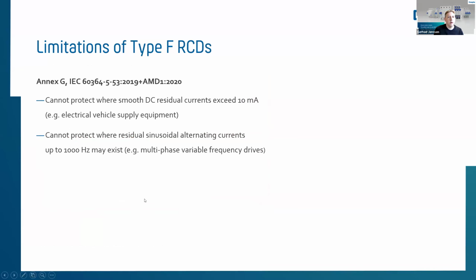What are the limitations of F RCDs? It is not able to protect smooth direct DC currents exceeding 10 milliamp, again charging equipment, for example. It also cannot protect where residual sinusoidal alternating currents go up to 1000 Hz. So if frequency drives, VFDs, are involved, then again a type F is not the best solution. Then you would need a type B.